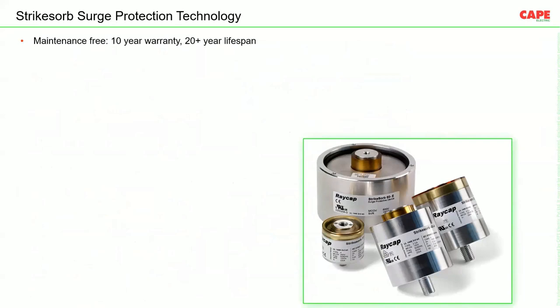Now, what are the other advantages of these bus bar mounted SPDs? They are completely maintenance free. Imagine we have installed a DIN rail mounted SPD in, let's say, a 3200 amps panel, in parallel connection with some flag indication. It's a parallel device. We don't know when it is going to fail. Let's say an SPD has failed after 2 years, in open circuit mode. It disconnected itself. How are we going to know? Unless we physically check the panel, we won't know whether the SPD is working or not. And practically in India, it is very rare. Maybe once in 6 months only we are going to check the panel. So in that case, our system is left unprotected.